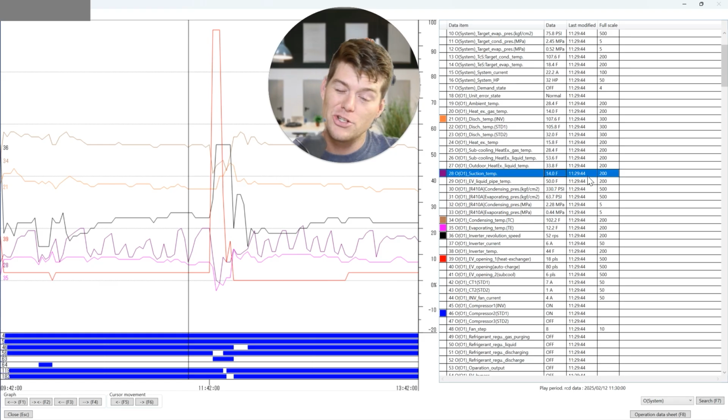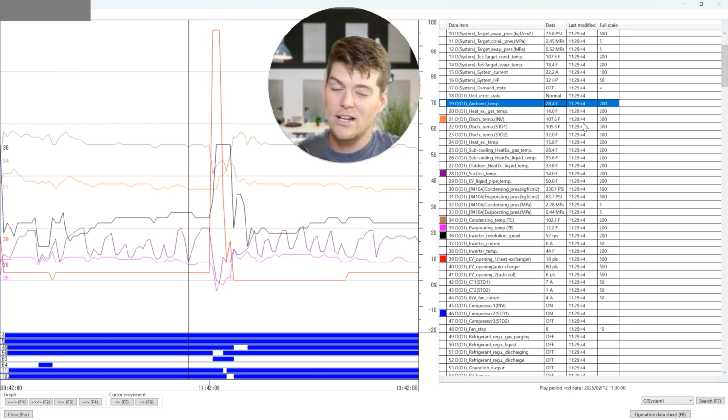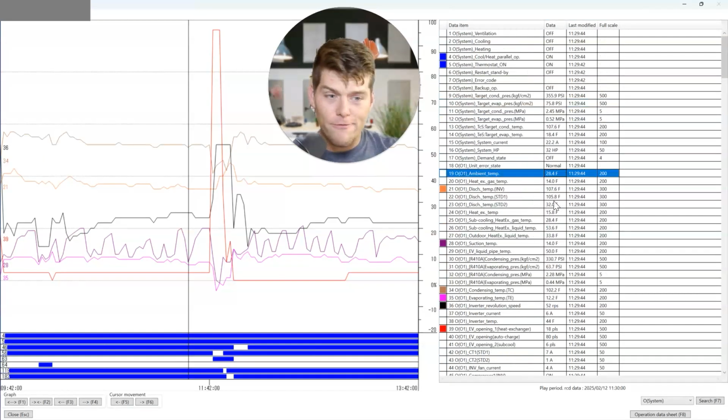And so sometimes it can be extremely misleading as to where the liquid might be because of these low ambient conditions. And a lot of times you see things that don't make sense because, again, the ambient conditions, if a coil's not operating, we might find that, hey, those sensors are actually the same as ambient. It's not actually liquid refrigerant coming back. So, all right, first thing, rapid fire.